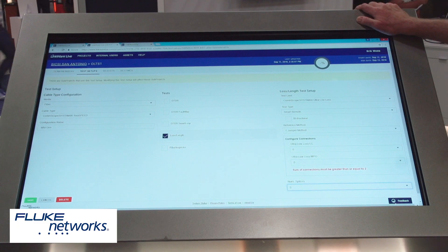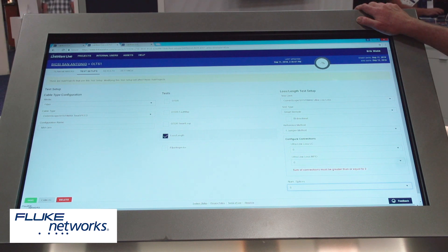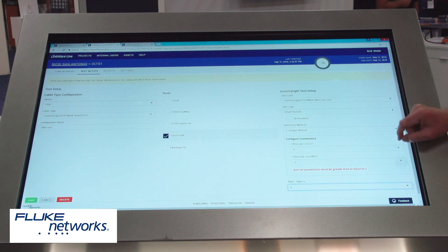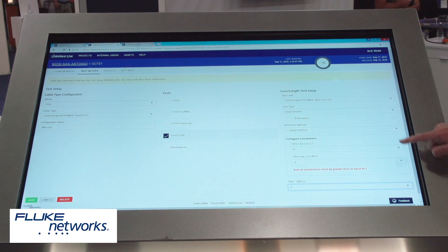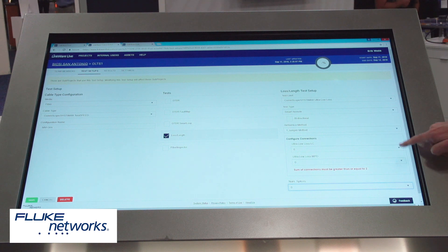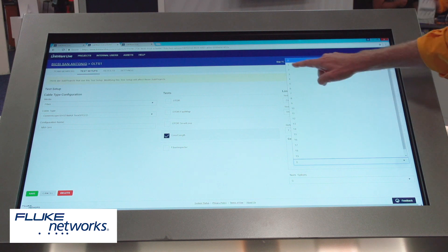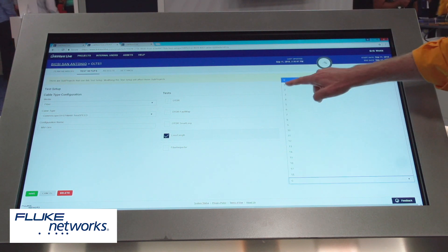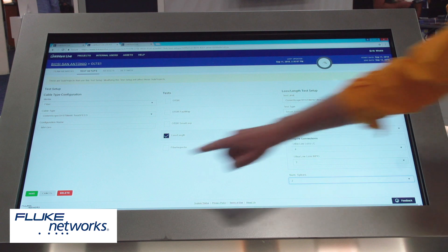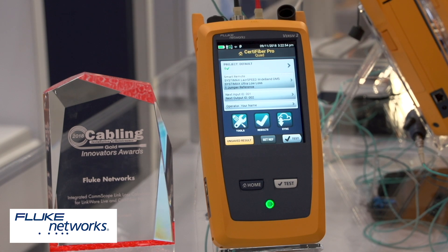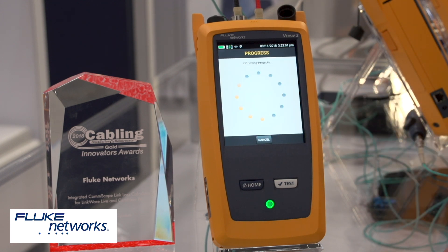Let me show you how you do it with LinkWare Live. The project manager, who doesn't have to be on site, simply brings up the configuration, sets the test limits for the CommScope SYSTIMAX Ultra Low Loss, then selects the number of connections — the number of ultra low loss LC connections and the number of MPO connections in the link — and finally the number of splices. Once that's done, he can save the setup and it's ready to be loaded into the tester. The technicians at the job site merely need to connect to Wi-Fi and then touch the sync button to download the settings.